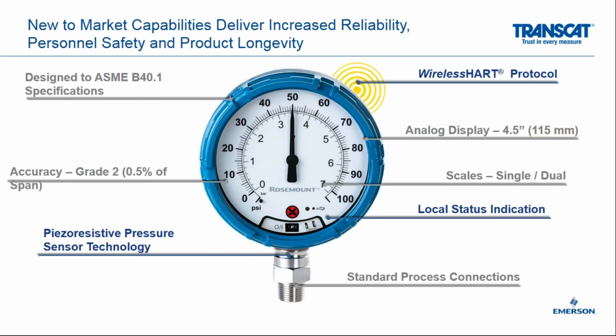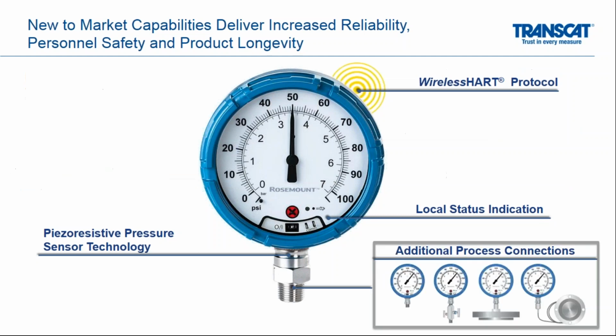In addition to all of those things that make this wireless pressure gauge a standard gauge, there's three unique pieces. First is wireless HART protocol. Again, I'll talk about that later in this webinar. And then the other two on the bottom left, we're actually using a piezo-resistive sensor technology. So there's no Bourdon tube, there's no process going into the gauge at any point in time. And then the other piece that we have is a local status indication. It's not an LCD screen that's going to play a sports game on it. What it is going to do is give you a red light, green light indication that can tell you if something's good or bad about the gauge without just relying on the needle to tell you that. And then finally, like any gauge, you can put something like a manifold or a flange on one of these gauges because the standard process connection is just like any other gauge.